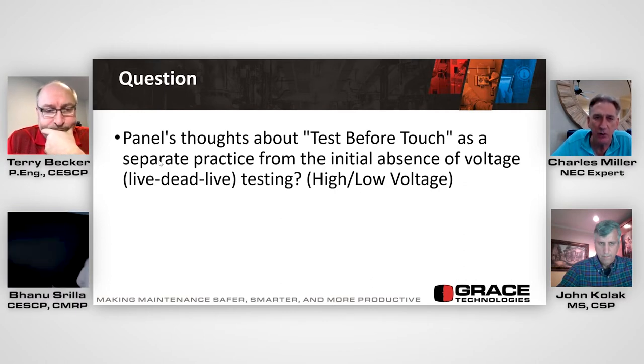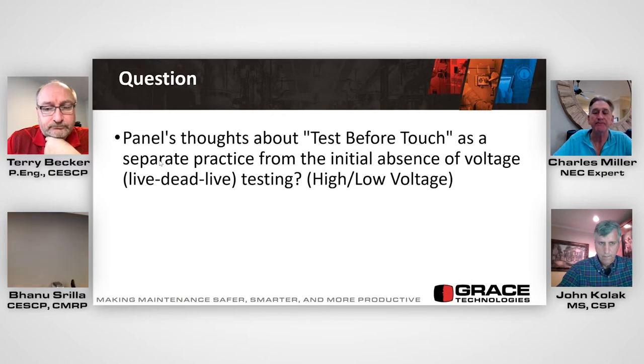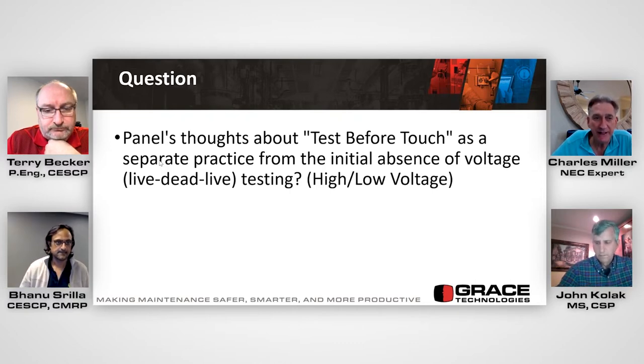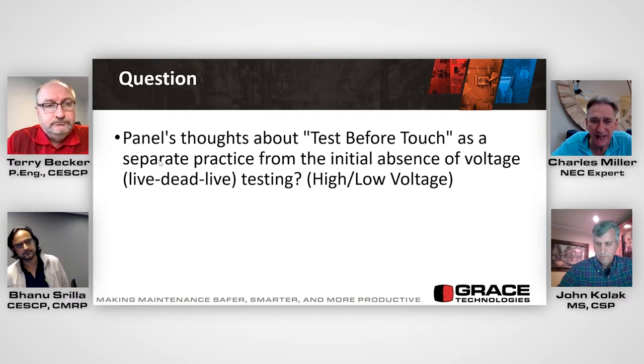So typically 480 volts and below, it's going to be seven steps. As long as those seven steps have been established and verified, the equipment is in an electrically safe work condition. The Grace product for testing the absence of voltage on the outside of the cabinet is perfectly fine.